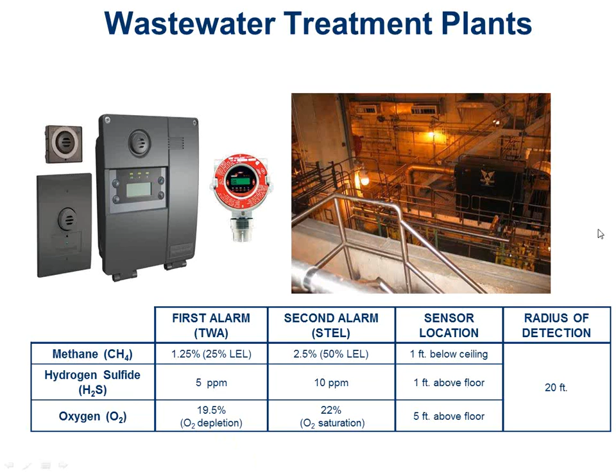Methane is a common one that we would measure. Hydrogen sulfide, which is that stinky egg odor or whatever you want to call it, is another one. That guy has a 5 part per million threshold. I want to control it below that. If I get to 10, I want to alarm. Hydrogen sulfide is heavier than air, so I measure it down at the floor. And then I typically want to measure oxygen to make sure I don't have too little or too much going on in there. So there's lots of work to be done in a wastewater treatment plant if you're into gas detection.